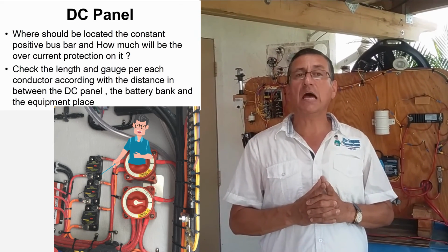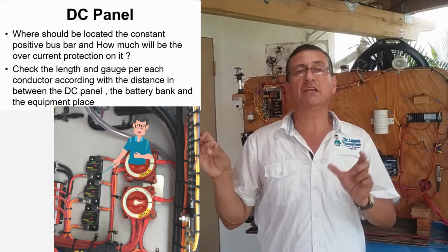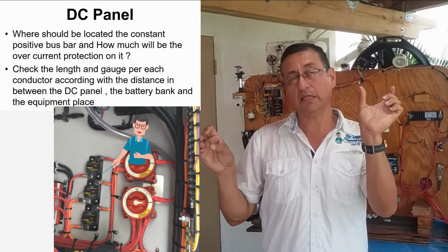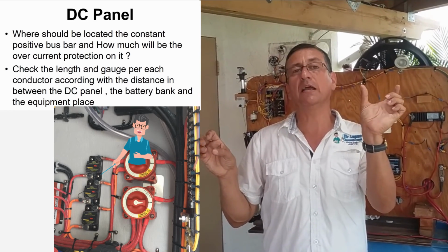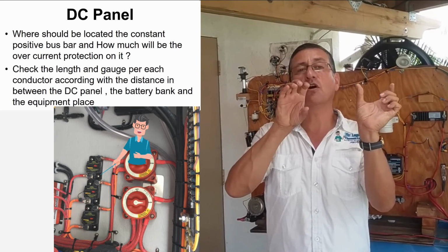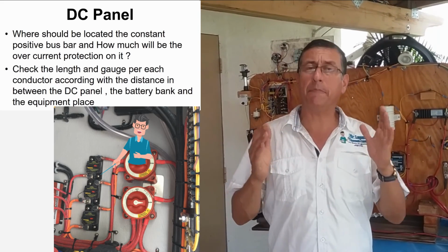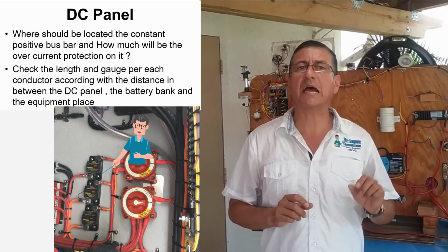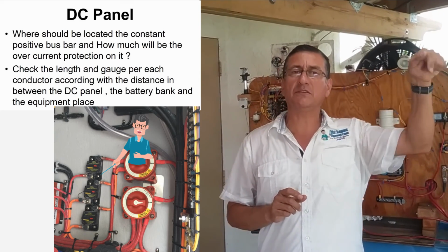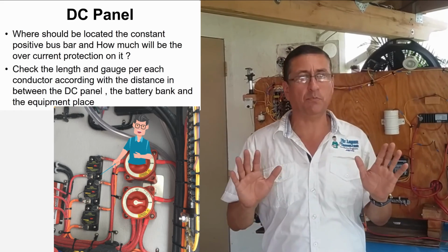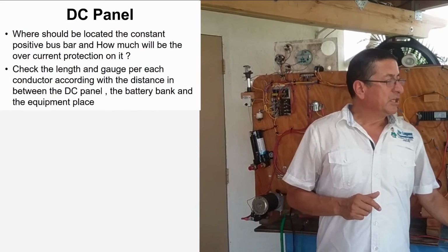You need to install a fuse between the positive of the battery and the positive constant bus bar for overcurrent protection. The capacity should be calculated according to the consumption of the equipment connected in the positive bus bar. It's simple.